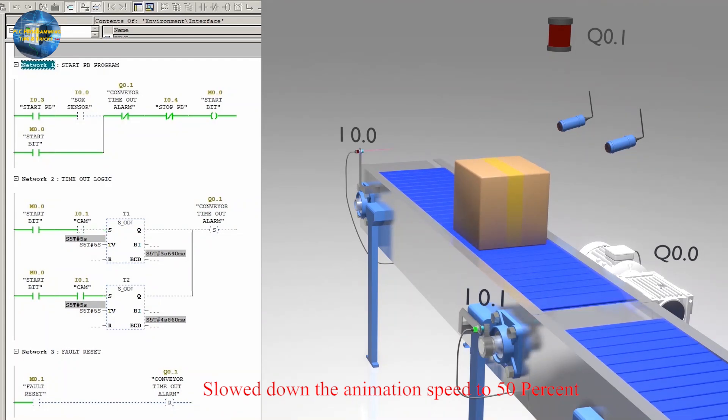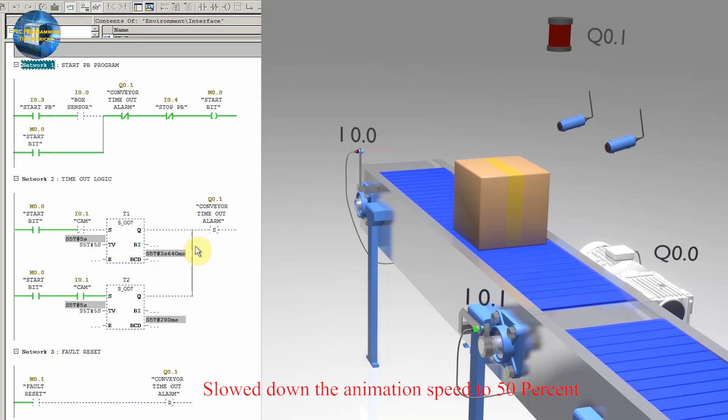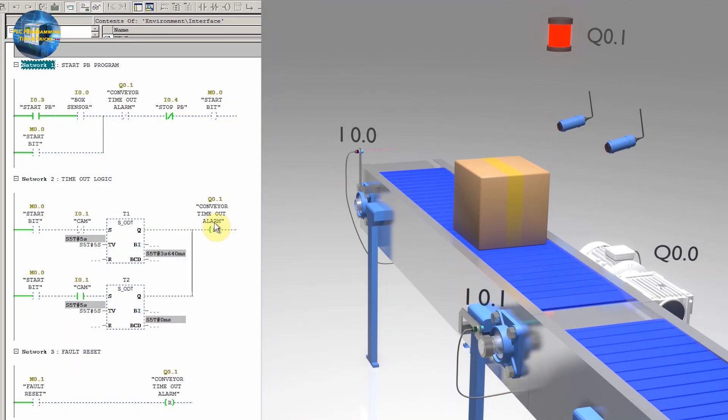As the conveyor belt stops, this time the cam is in front of the sensor I0.1. This time the T2 timer starts via normal open contact of the sensor I0.1. After 5 seconds, the T2 timer will activate the output Q0.1 which is our alarm buzzer.